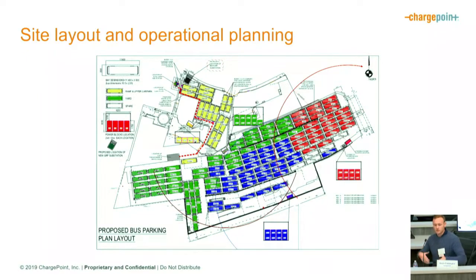Once we did the modeling to understand what that primary service level looks like and how much equipment we need, we were able to strategically map out where we wanted to land the switchgear to support the equipment needs. With DC charging equipment, there's a limitation in how far you can have your charging station from the remote dispensers, so the red rings map out where the DC capacity is within that yard.